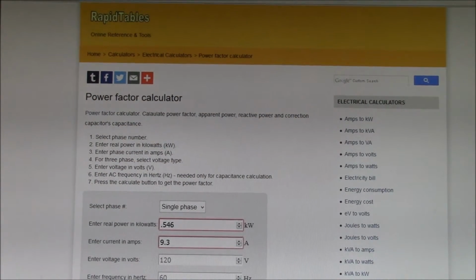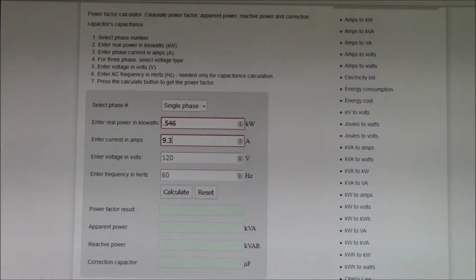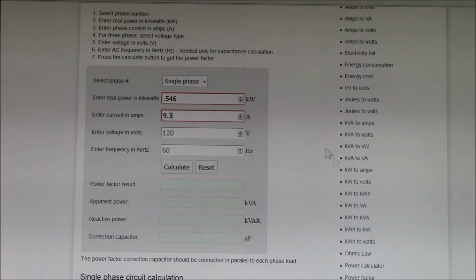So let's take a look at those power factor numbers that we measured on the video. This is on rapidtables.com. It's their power factor calculator, and I'll put a link to this in the video description if you want to check it out. Pretty easy to use. I'm running single phase. I entered the power that the kilowatt meter measured, 546 watts, 9.3 amps. I hit calculate, and down here at the bottom gives you a value of a correction capacitor that would correct the power factor on this washing machine motor. And it says about 180 microfarad.